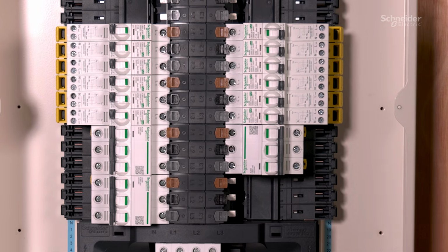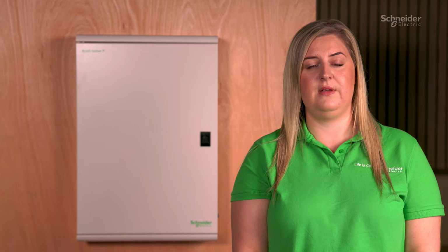So let's see how easy it is to fit into our Acti9 distribution board. On all boards, the SPD should be fitted as close to the incomer as possible. In this board, you can see we have left a space for it on the right-hand side of the stack. First, we need to pull back the locking clip to allow ease of fitting.